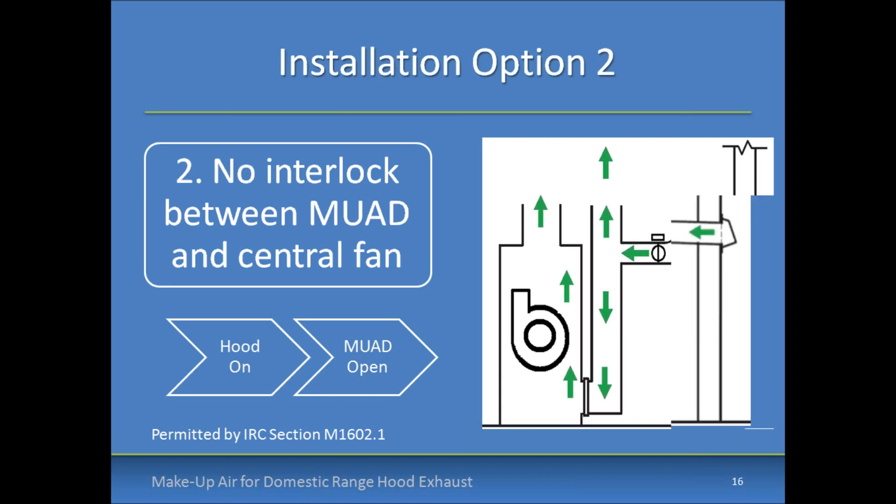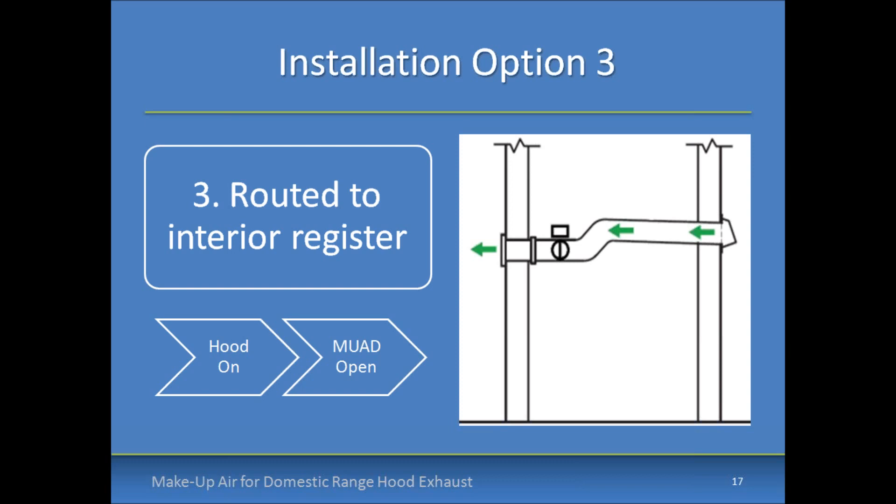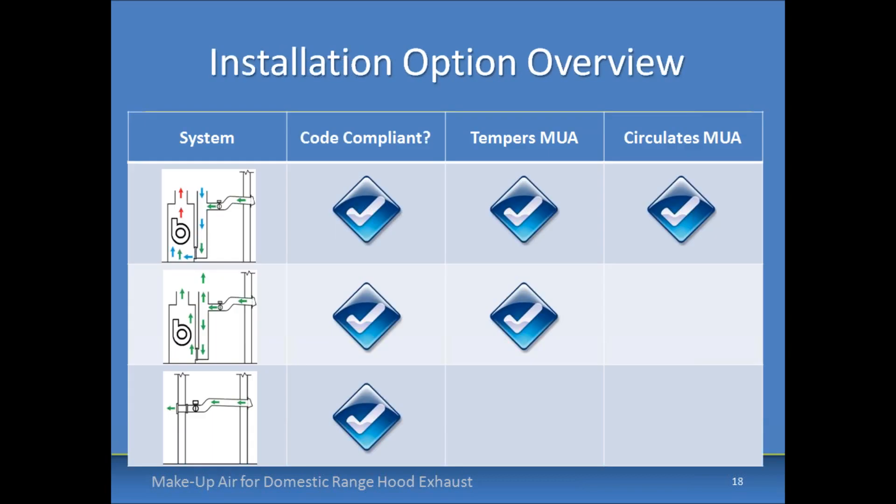With the non-interlocked return trunk option, you have less tempering since air doesn't pass over the heat exchanger, but you do have some mixing before it reaches the kitchen. A disadvantage is that less flow is provided because you don't have that central air handler boost. The third installation option is routing the make-up air damper to an interior register, not integrating it with the duct system at all. This is the simplest code-compliant option, but it doesn't have the advantages of tempering or mixing. Broan recommends not dumping the make-up air right on top of the range hood, as that could cause short circuiting.